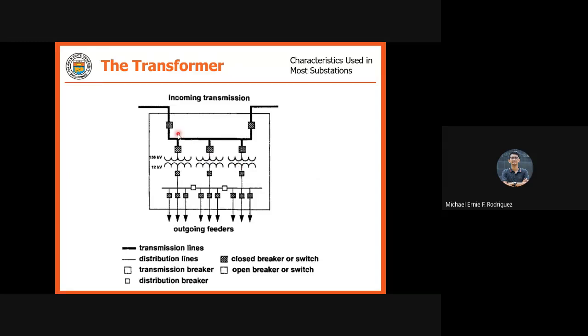What we have is this. In this case, we have two transformers, and each transformer has its own bus. You have only a tiebreaker, which is normally open, an open breaker or switch. So this is the style of our Paleco substation. In the drawing, we have 3 transformers, and a separate bus for each transformer interconnected by an open breaker or tie breaker, and then going to feeders. We have 3 feeders for each transformer.